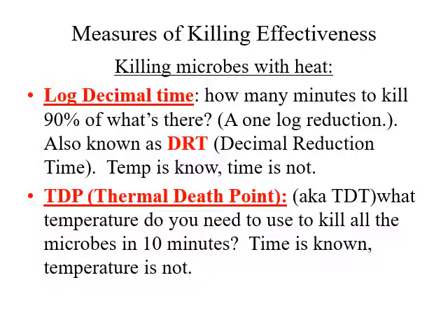Okay, so as we already mentioned, the log decimal time, or the decimal reduction, 1 log decimal reduction, DRT, decimal reduction time, is how you know, with the temperature that you're using, 100 degrees or 120 degrees, how long do you have to leave the object that you're trying to sanitize or sterilize in that temperature in order to kill 90% of what's there? So that's called a DRT.